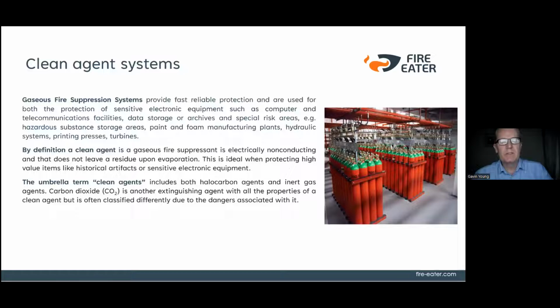Clean agent systems, gaseous fire suppression systems, fire extinguishing systems, gaseous extinguishing systems, they're all more or less the same thing. It's a gas that goes into the extinguishing system. A gaseous fire suppression system provides fast, reliable protection and is used for the protection of sensitive electronic equipment such as computer and telecommunication facilities, data storage, and archives, and special risk areas such as hazardous substance storage, paint booths, foam manufacturing plants, hydraulic systems, printing presses, and turbines. The definition of a clean agent is a gaseous fire suppressant which is electrically non-conducting and does not leave a residue upon evaporation. This is ideal when protecting high-value items like historical artifacts or data centers with sensitive electronic equipment.